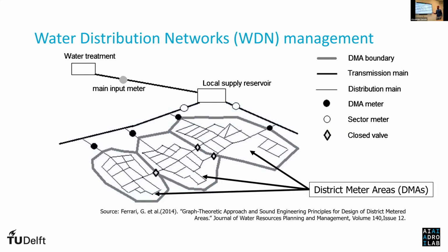And then, in order to control better what we have in the system, water companies change and direct the water from one pipe, where there is a DMA meter, in order to create small areas that are more controllable and that just have one access to the water. These areas are called district meter areas. That's why I say DMA meter. So you pass from here, and then you have a distribution around the areas. See here, you see 3 different district meter areas.